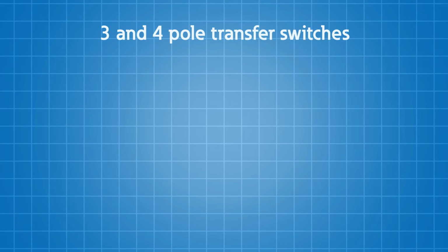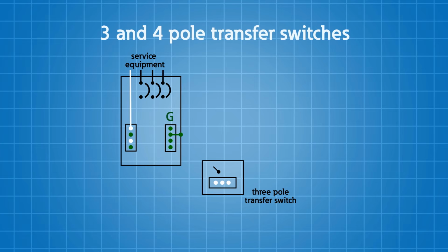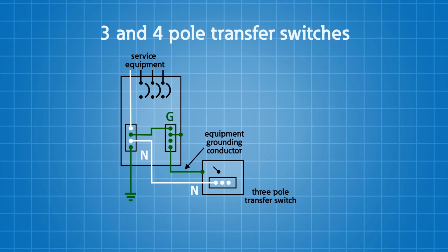For systems with transfer switches, if separately derived systems are to be joined via a transfer scheme, only one neutral to ground connection must exist. Let me show you how you can accomplish this with a typical power system. So let's take a quick look at an example system where you would have a transfer switch, and obviously you have your utility and your service panel. Off of your service panel, you'll have your grounding electrode. Your grounding electrode conductor will come up to your neutral bar, and then you'll have a bonding strap between your neutral bar and your equipment grounding bar.